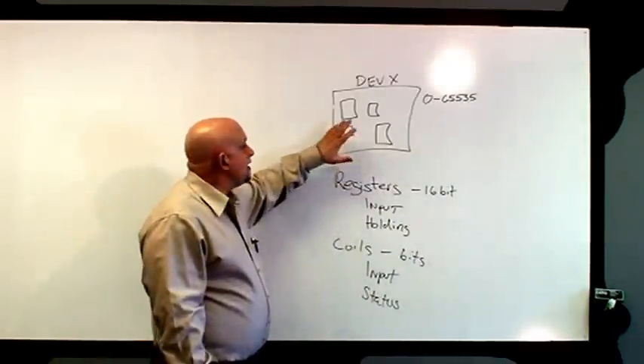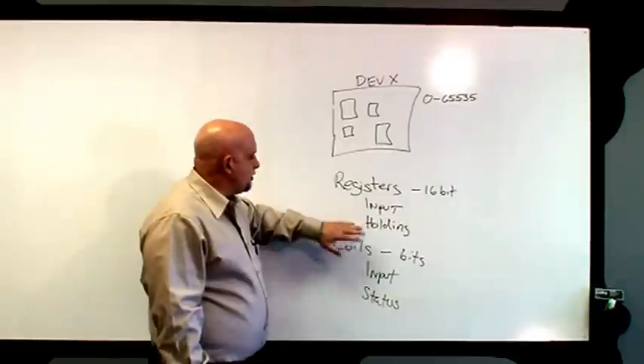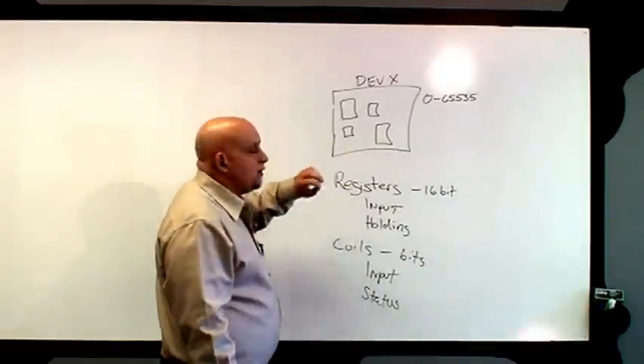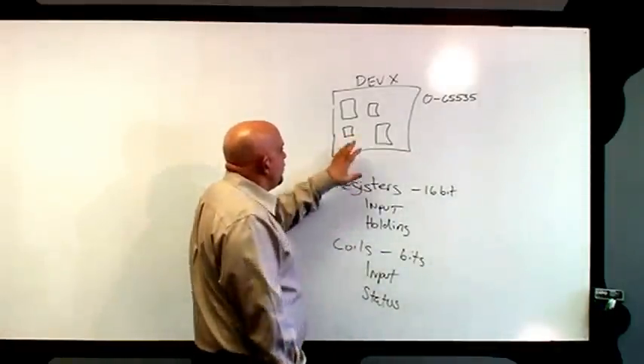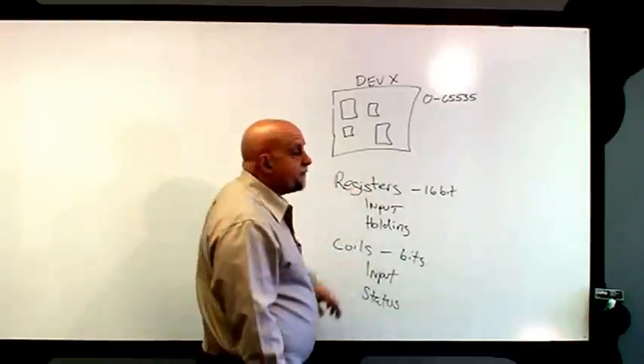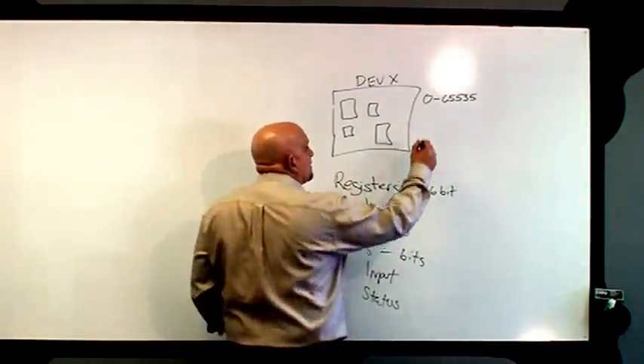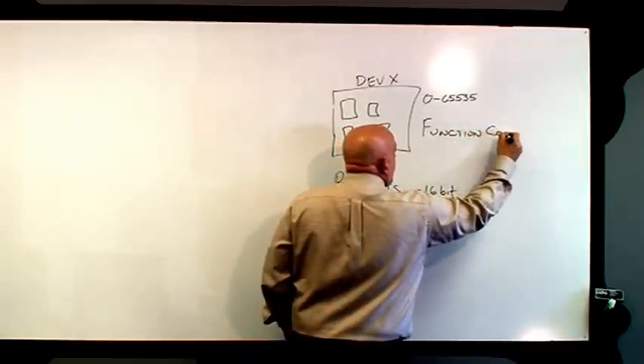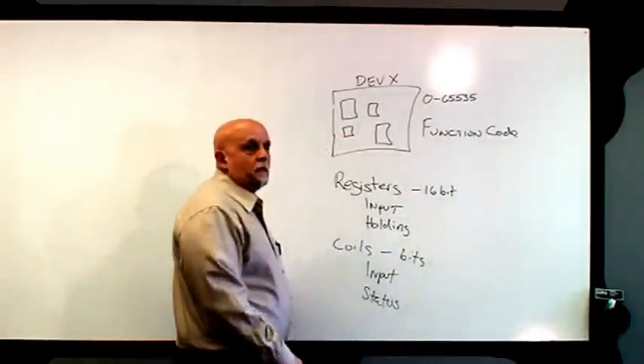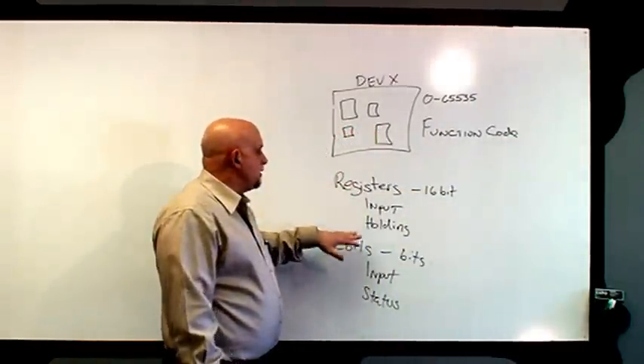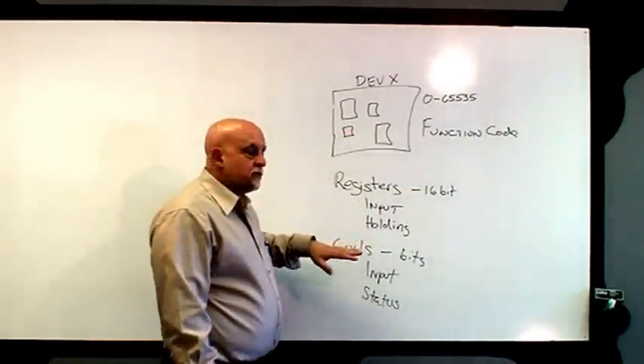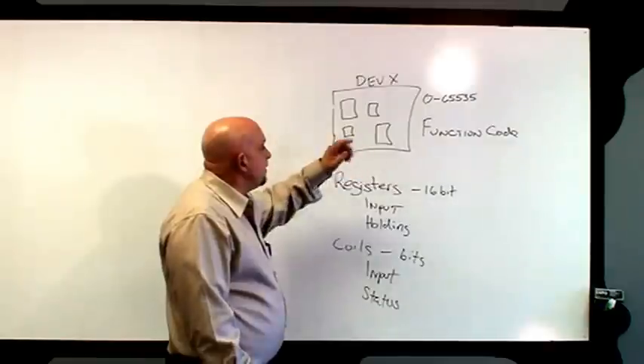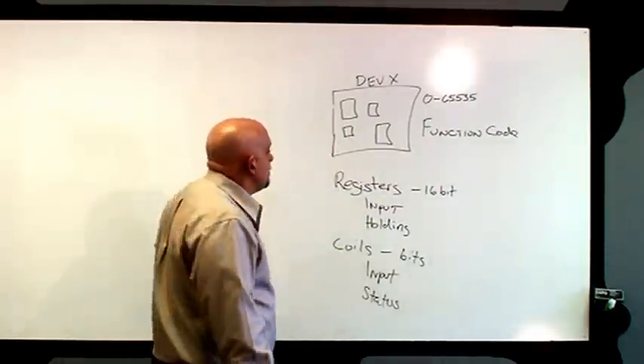So what they typically do is limit this — for example, we're going to have 10 holding registers and 16 input coils, and that's it. Once these data areas are defined, a Modbus master uses function codes to access them: read registers, read holding registers, read input registers, set a holding register, read input coils, and so on. We've talked about that before and won't review it today.